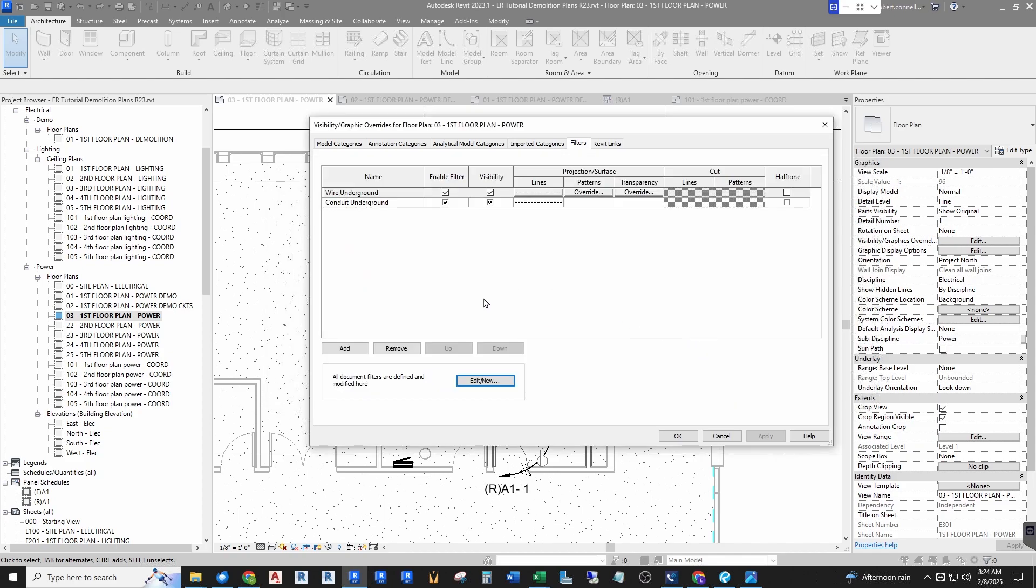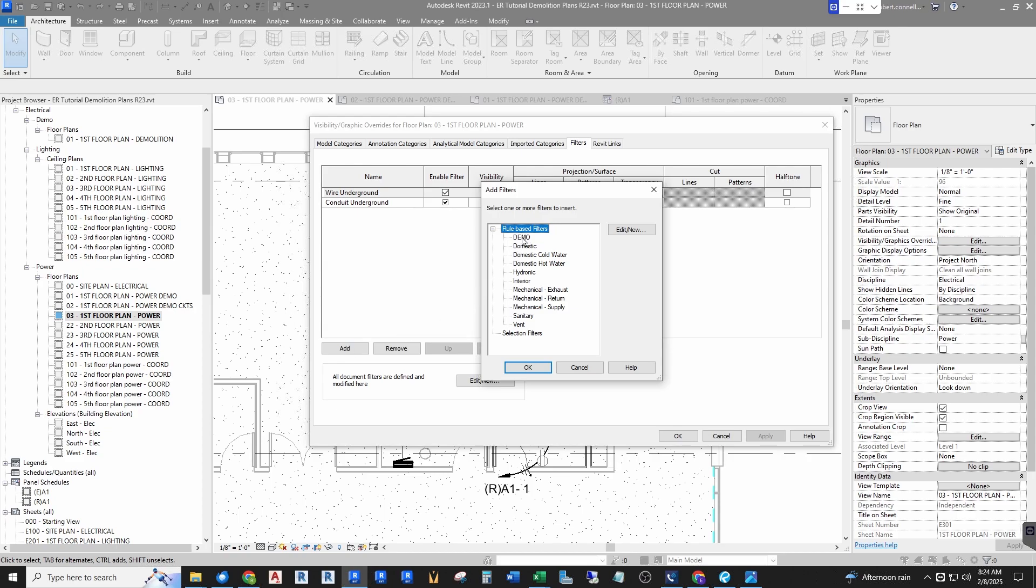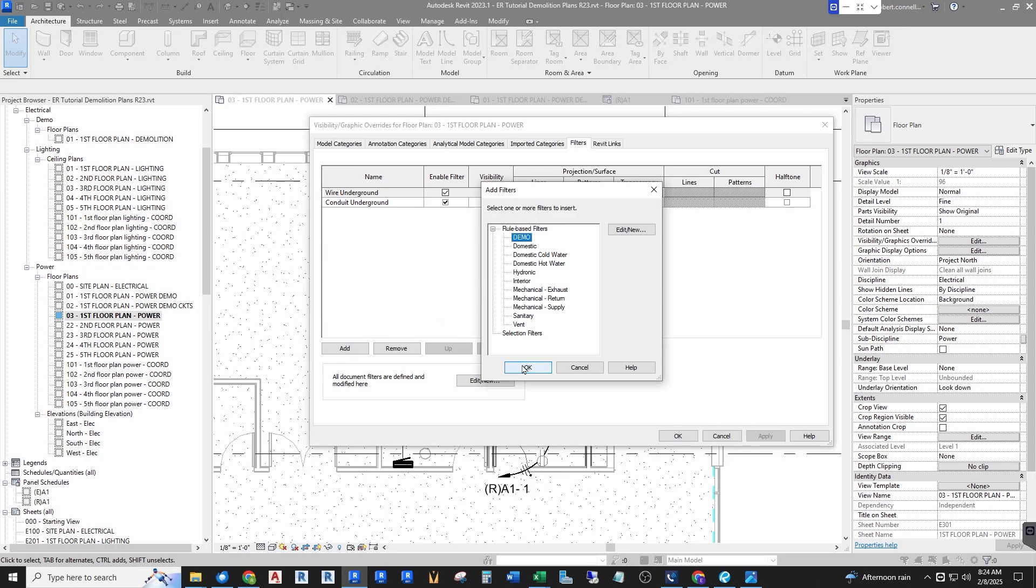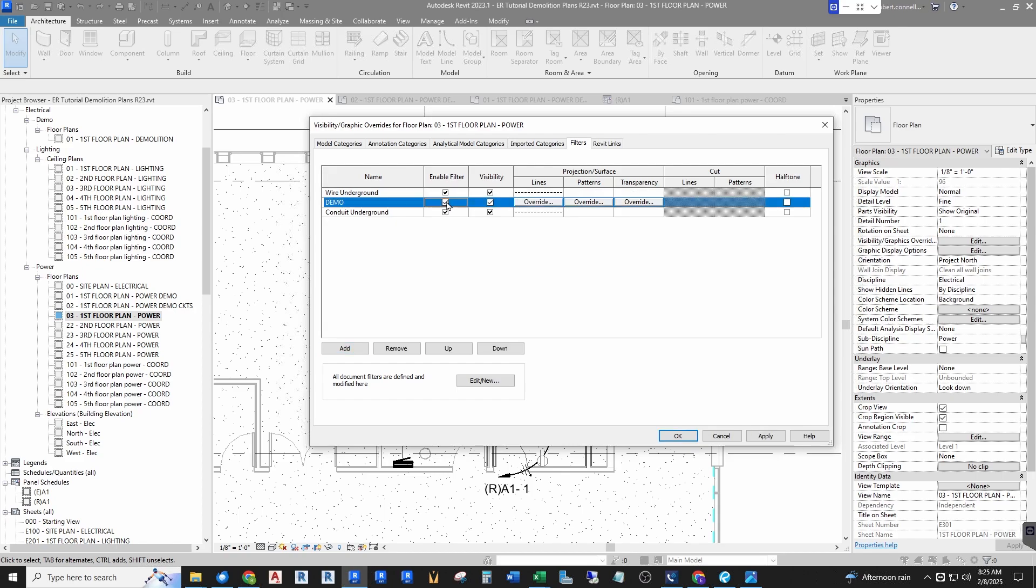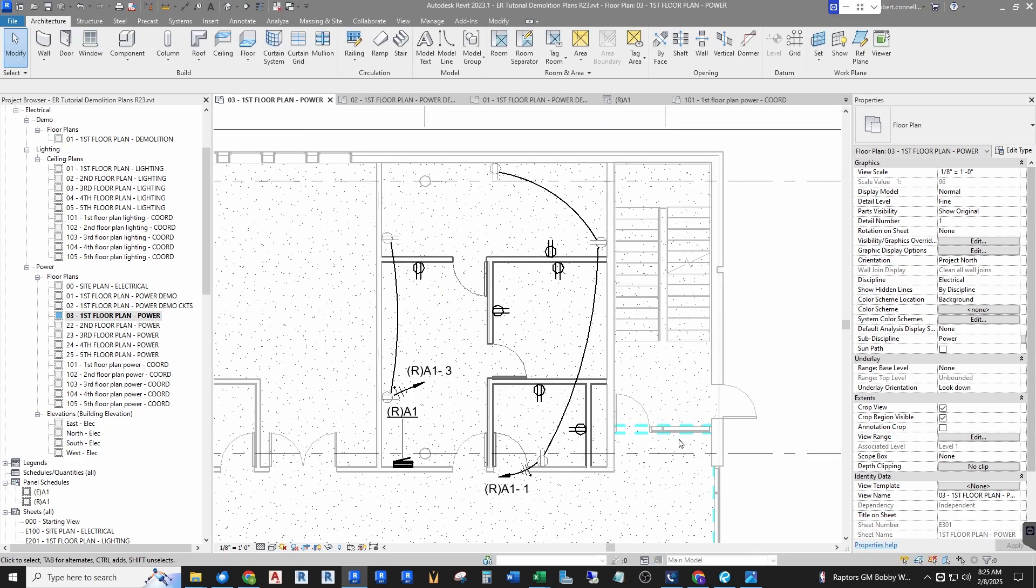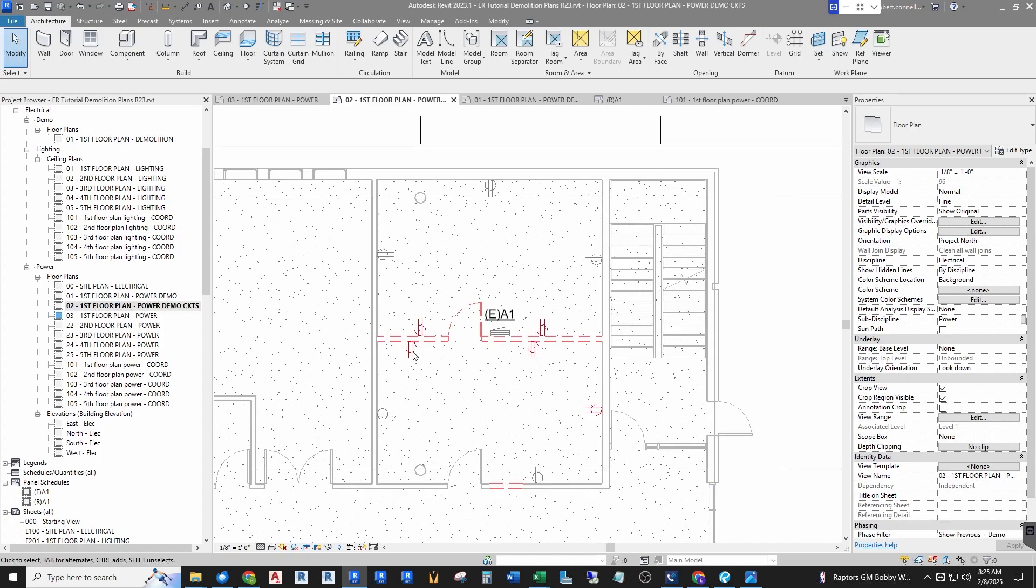Now this is where I control what happens with that selection. I'm enabling the filter because I can turn this on and off at will. Do I want to override any of the line types or patterns? No. But I do want to control the visibility of anything that says demo. I actually want it to be not visible, so I'll uncheck it. So this just means I can even make a halftone. This just means that now anything that has the word demo in the comments section will be turned off. So it's another method of control. And as you can see my panel, existing demo panel, disappeared in this view. But it did not disconnect all the circuits because I didn't actually demo the panel with the phasing situation. So it's still there.